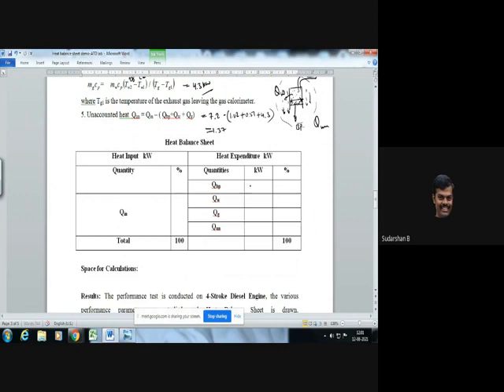So all these things you have to put here. The total heat input is 7.2, BP is 1.02 - you calculate the percentage. Water is 0.51, gas is 4.3, and unaccounted is 1.37. If you calculate this you will get directly 100%, work out the percentages, and adding up will give total heat input of 7.2. This is how you draw the heat balance sheet.